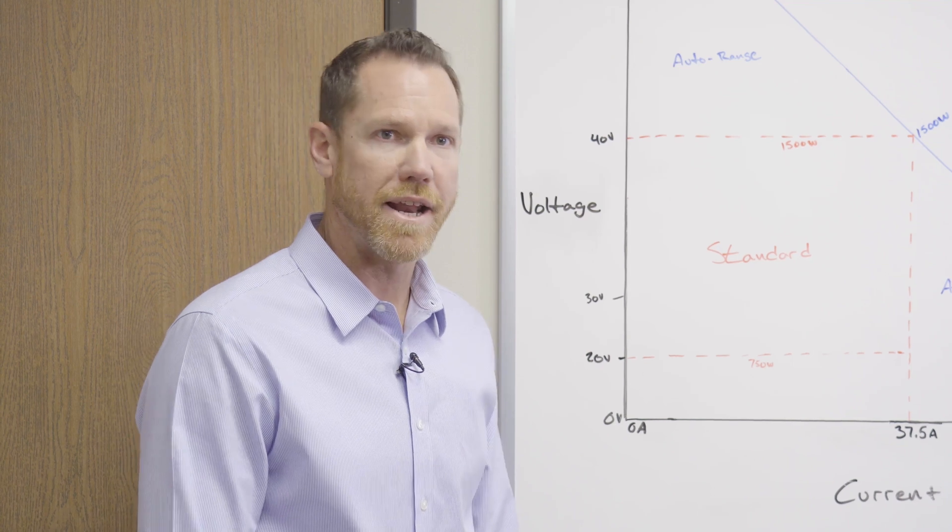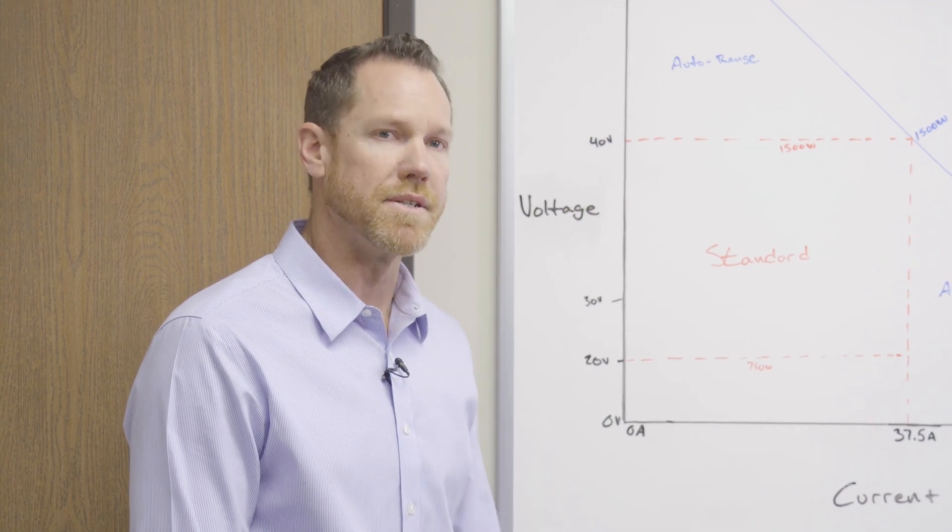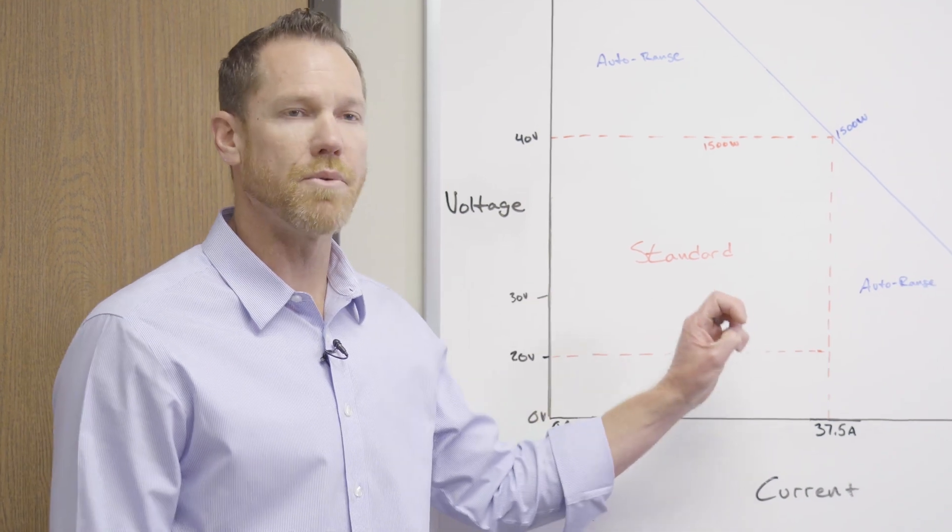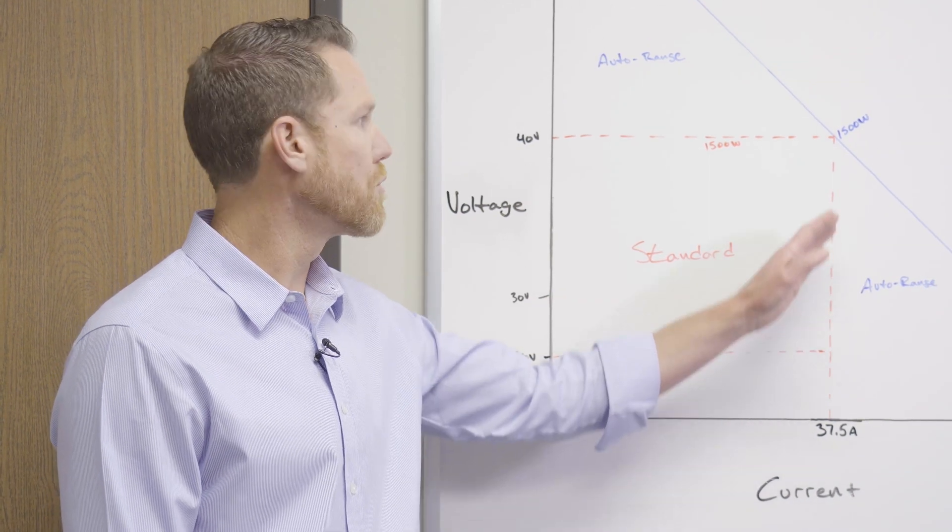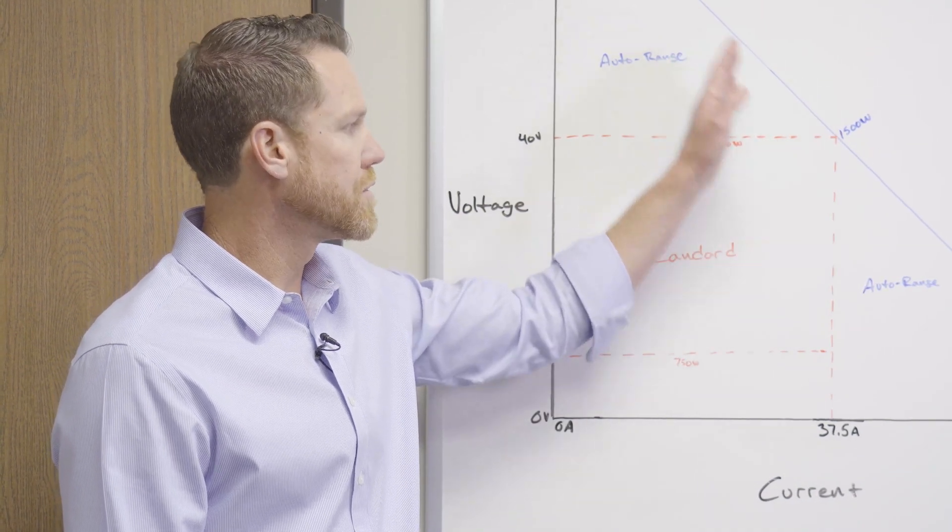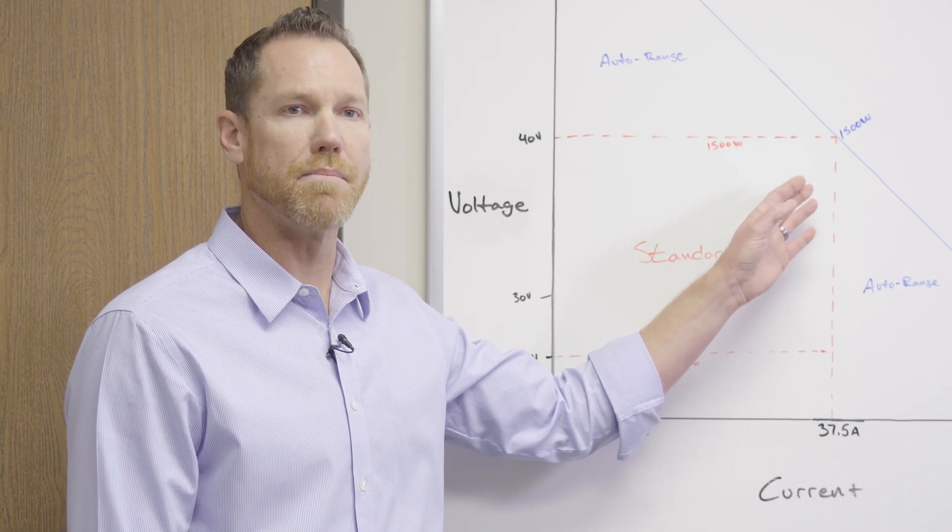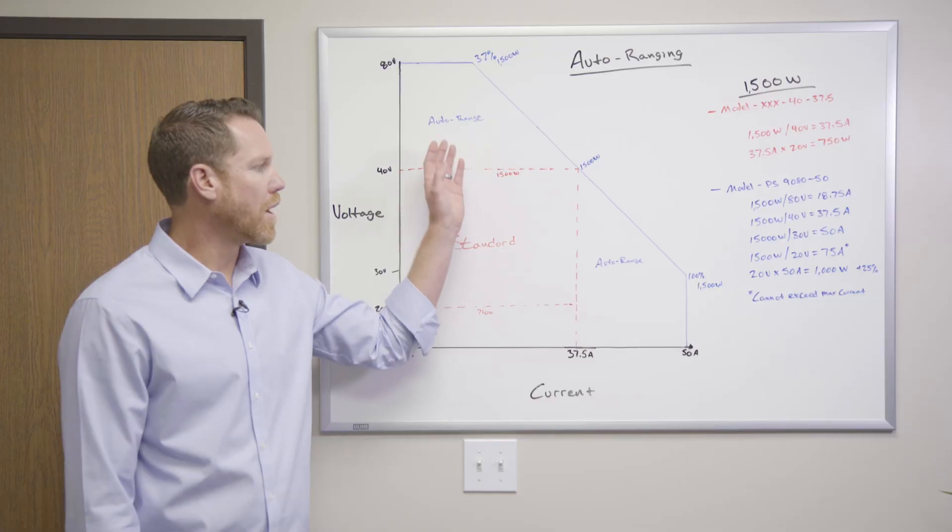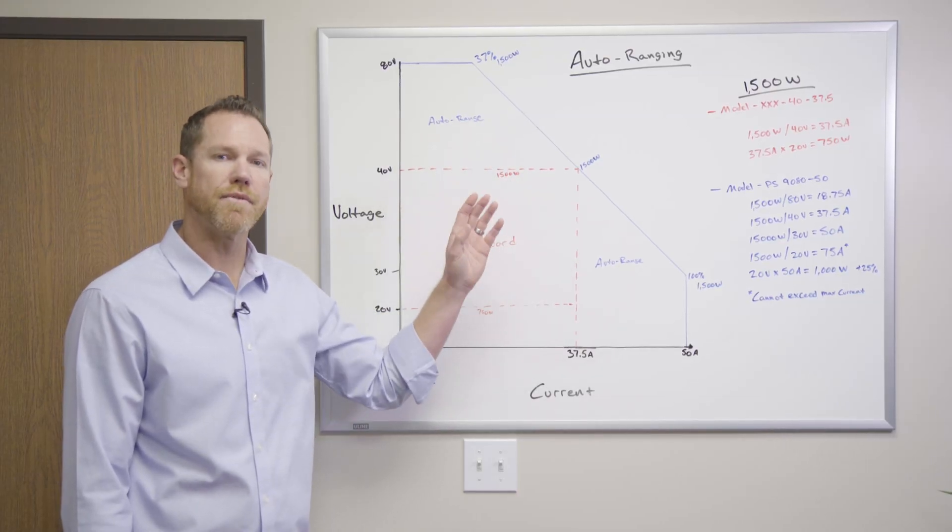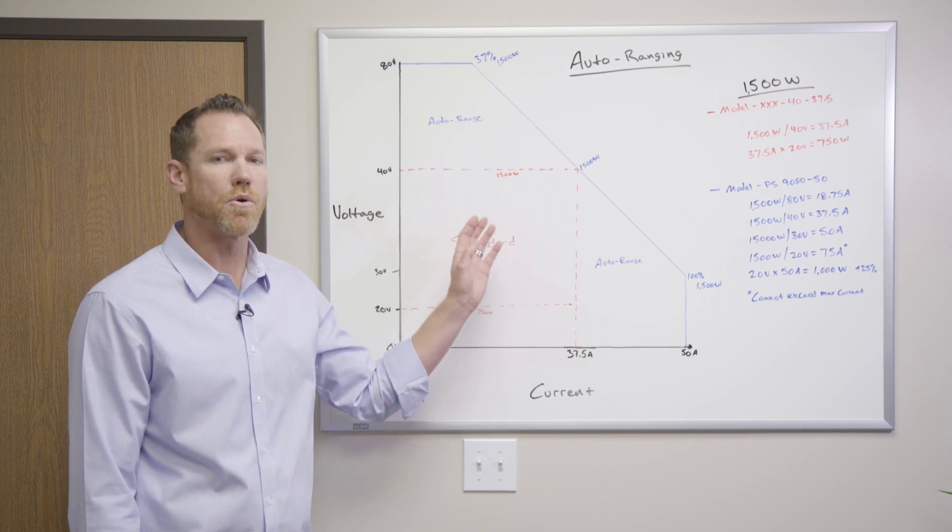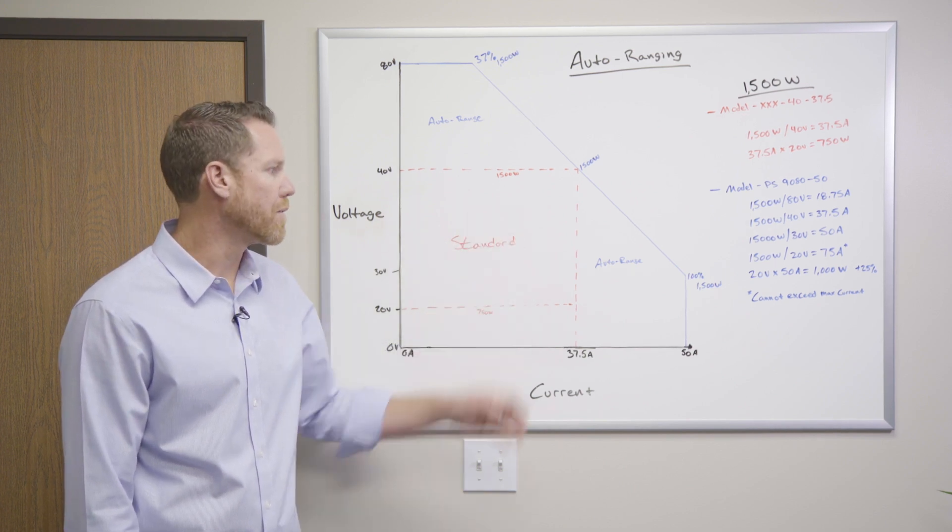Now, EA Elektro-Automatik power supplies work a little bit differently. This feature is called auto-ranging. What auto-ranging will actually do is as you program either up in voltage or down in voltage, the current that is available from the output of the power supply will actually increase or decrease as a function of the program voltage to maintain constant power across a wide operating range.